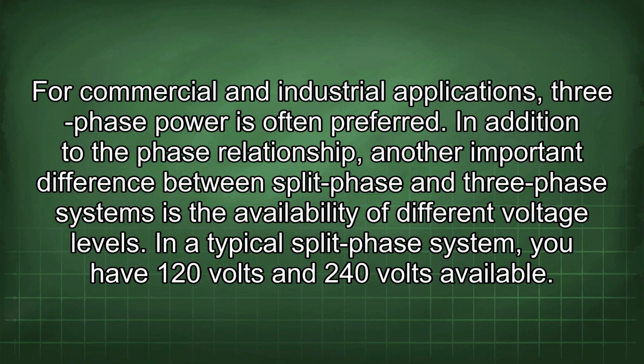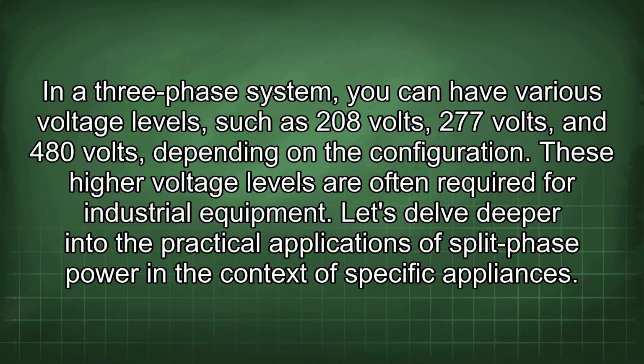In addition to the phase relationship, another important difference between split-phase and three-phase systems is the availability of different voltage levels. In a typical split-phase system, you have 120 volts and 240 volts available. In a three-phase system, you can have various voltage levels such as 208 volts, 277 volts, and 480 volts, depending on the configuration. These higher voltage levels are often required for industrial equipment.